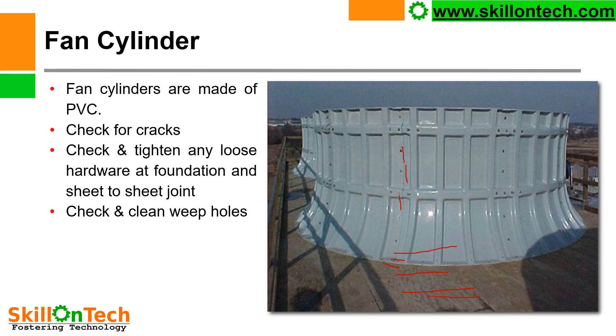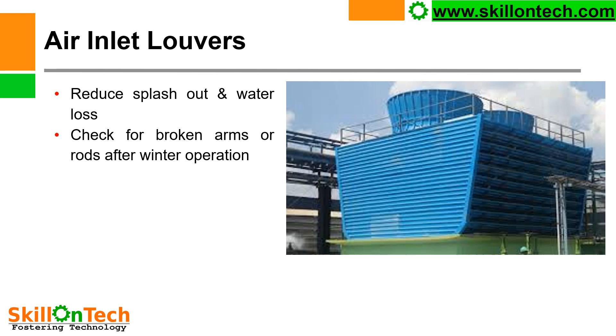Sometimes fan cylinders are tied with steel ropes to nearby rigid foundations to stop them from being damaged during high wind flows. Because during high velocity winds, these fan cylinders may get damaged, so they shall be protected by tying with tie ropes. Air inlet louvers — you can see in this picture these are the air inlet louvers. Air enters through the louvers inside the cooling tower. These louvers reduce splash-out and water loss into the atmosphere. If any louvers or their arms are found broken, they shall be replaced.